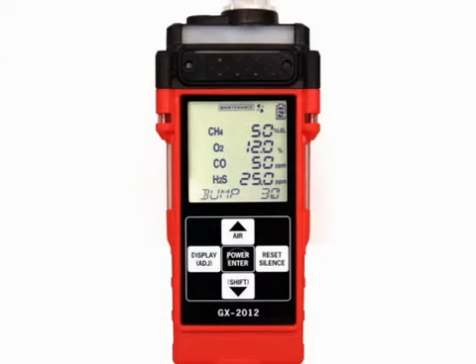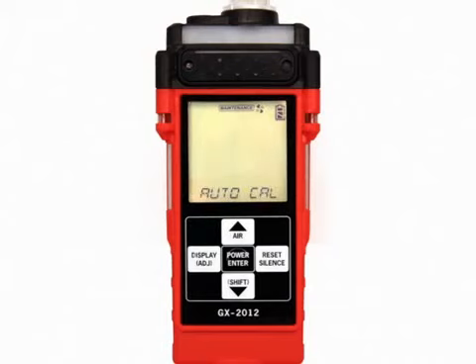A bump test may be performed on the standard 4 sensors or on the percent volume combustible sensor. Use the air or shift buttons to display the screen for the sensors you wish to bump test. Before proceeding, confirm that the bump test gas values are the same as the concentrations on the calibration cylinder.